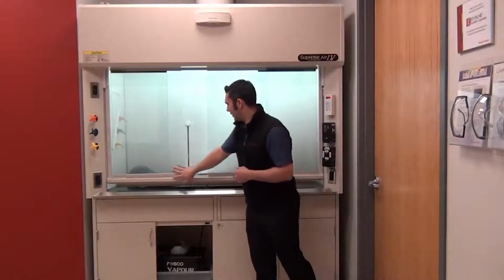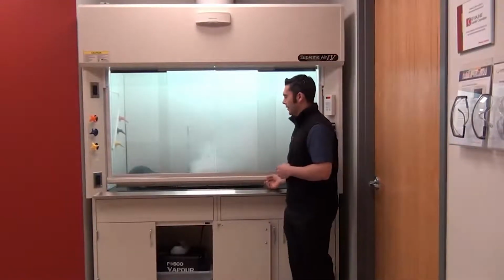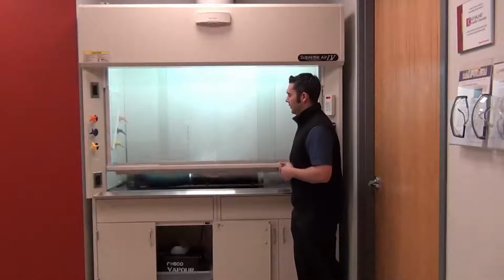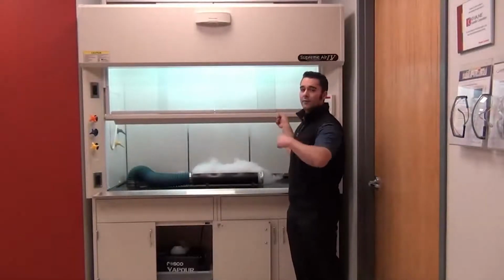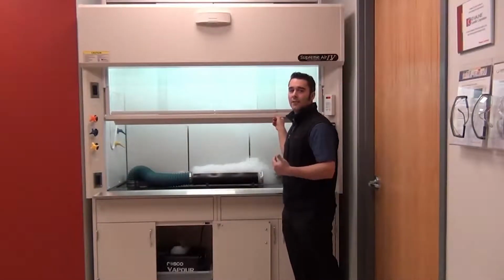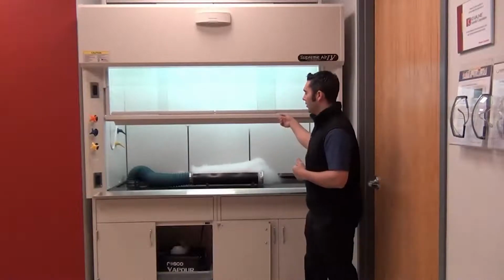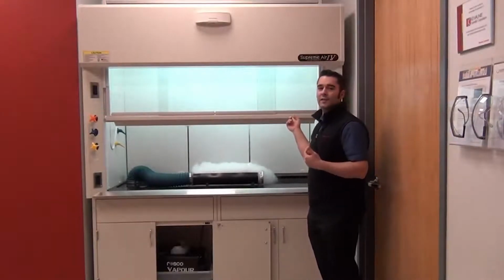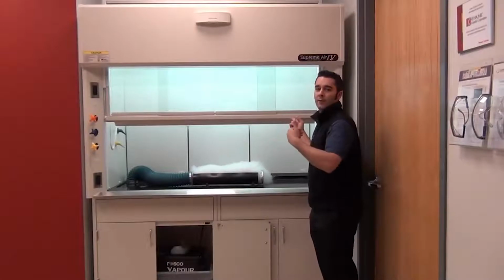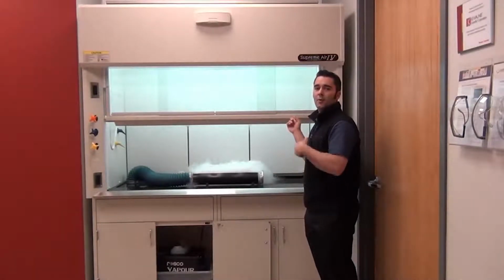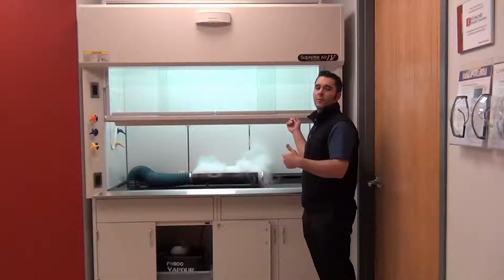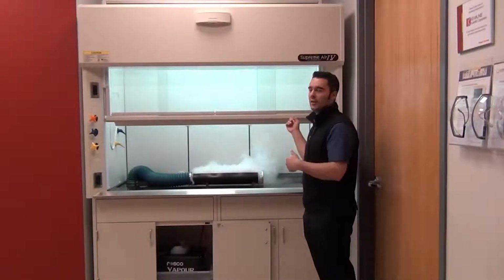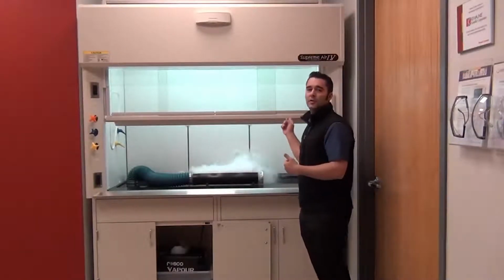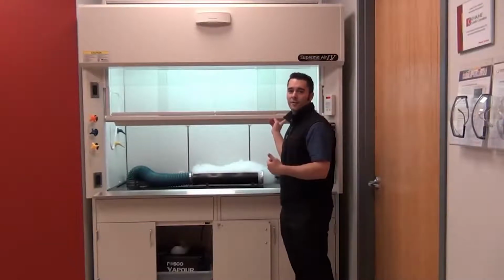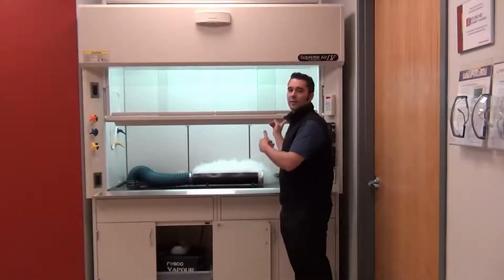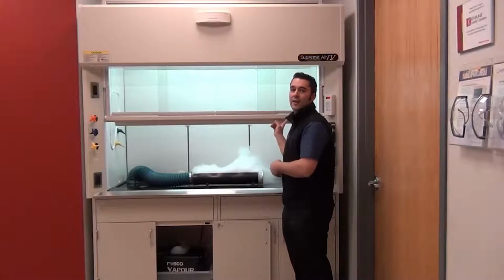So the speed of response, again, 1 second speed of response. No matter what sash I move on this hood, within 1 second my valve is going to respond, and I'm going to guarantee that I can have that containment inside of the fume hood. You'll also notice that once it's in its steady state, I don't have any puffing effect or anything inside of the fume hood, which would be indicative of a case where a fume hood would be sitting there hunting to try to maintain its set point. Because of the pressure independent aspect of the Phoenix Controls Venturi valve, I get very stable and steady control no matter what position I leave the sash in.